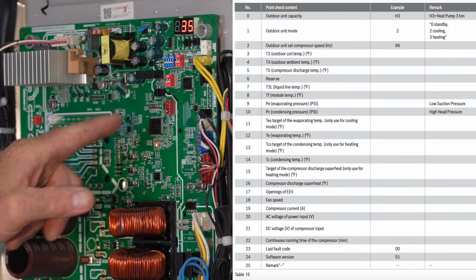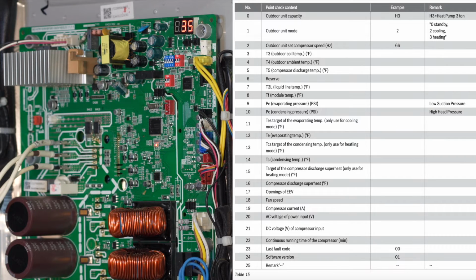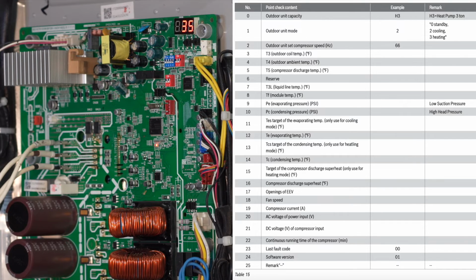And that represents SW4 number 4? Correct. Okay. Number 4, yes. So once again, when you call in and we see that target temperature, we can tell whether you've manipulated that switch or not to the -4 or lower 4 degrees, or whether it's still at the factory setting. Number 12 was the actual evaporator temperature, was 39. Now, just like 11, 13 is your target temperature for heating. So that's 108. We know that's default out of the box. If you had flipped the SW4 number 4, that would show 112, and once again, we would know that you flipped that switch. Number 14 is the actual condensing temperature. It was 87. The 15 is the target of the compressor discharge superheat. That was at 37. Number 16, compressor discharge superheat, 41.